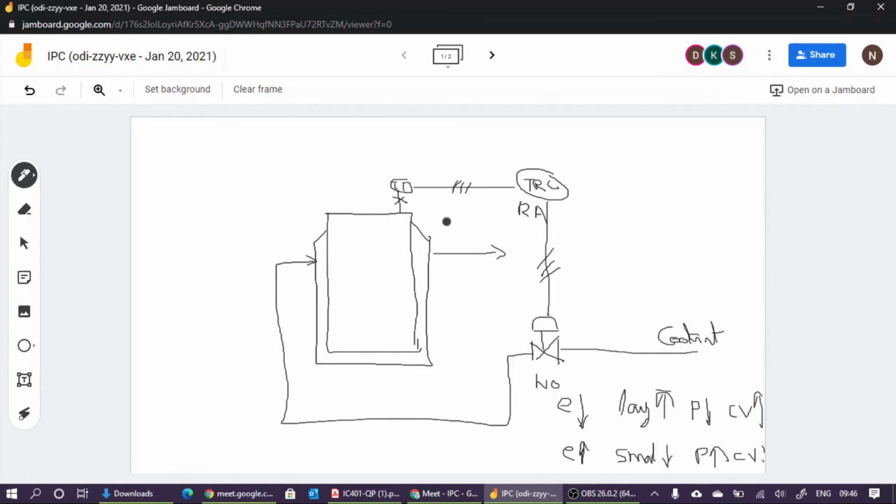So especially if it is polymerization, the required valve opening is normally something around 80 to 90%. If it is very close to 80 to 90%, then with respect to the variation of temperature, if we are trying to open the control valve from the normal opening, what will happen? We can expect 100% valve.